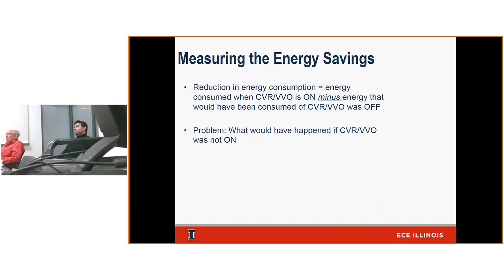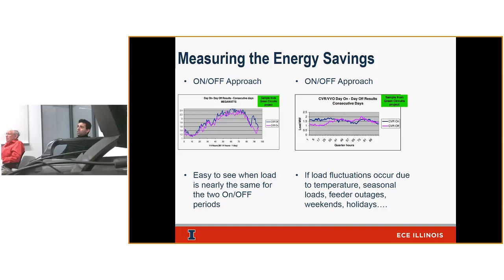Here's an example of an actual circuit over a number of hours where we had CVR on — shown in pink — and CVR off in dark blue. You can see the variation looked reasonable and the power was reduced overall. A good candidate circuit gives neat results. Another circuit could have weird results, especially with outages, large temperature fluctuations, seasonal loads, or missing data. The idea is to do on-off testing while normalizing for these fluctuations.